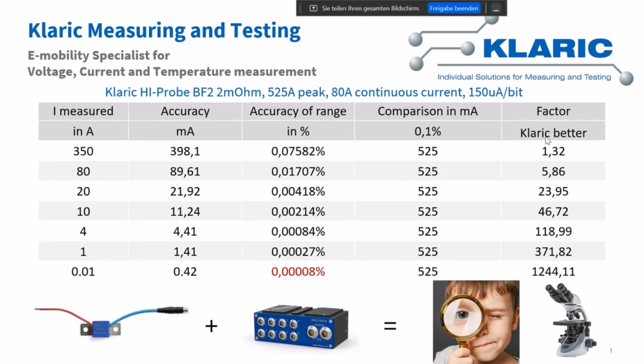Comparing this with existing products on the market, you can easily find sensors with an accuracy of 0.1%. From a 525 amp sensor, that means 525 milliamps of accuracy. Compare this with our accuracy, in the smallest range, of 0.42 milliamps. We are 1,244 times better than a sensor with 0.1%.